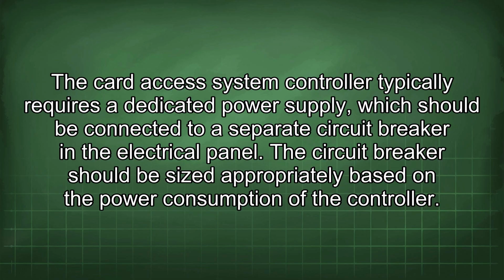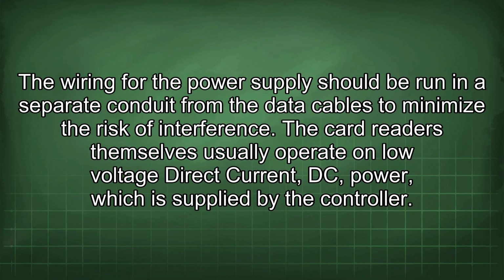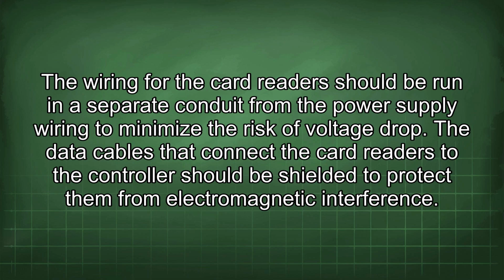The card access system controller typically requires a dedicated power supply, which should be connected to a separate circuit breaker in the electrical panel. The circuit breaker should be sized appropriately based on the power consumption of the controller. The wiring for the power supply should be run in a separate conduit from the data cables to minimize the risk of interference. The card readers themselves usually operate on low voltage direct current (DC) power, which is supplied by the controller. The wiring for the card readers should be run in a separate conduit from the power supply wiring to minimize the risk of voltage drop. The data cables that connect the card readers to the controller should be shielded to protect them from electromagnetic interference.